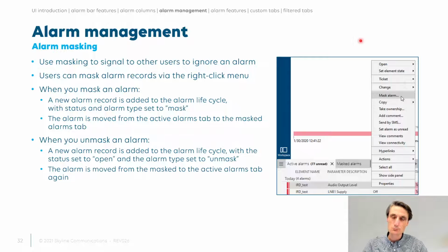Now masking. Masking is probably the most frequently used and most popular feature of the alarm management. Masking goes a step further because the alarm is really taken away, you could say. It is taken from the active alarms tab page and it's moved to the masked alarms, which is a little bit more hidden away. And moreover, it is also no longer impacting your overall alarm state of the element and all the views on top of that, in case you have it somewhere in the surveyor bubbling up.